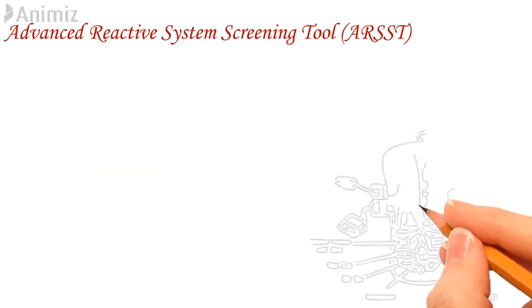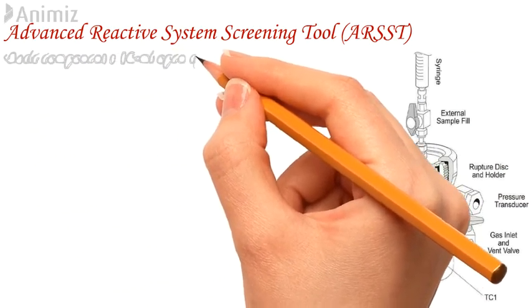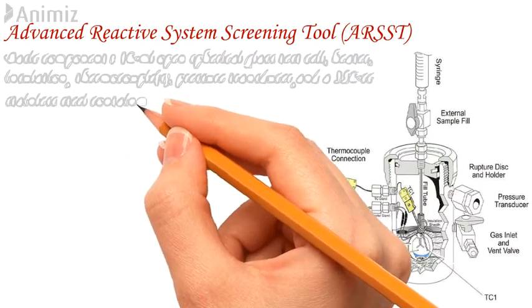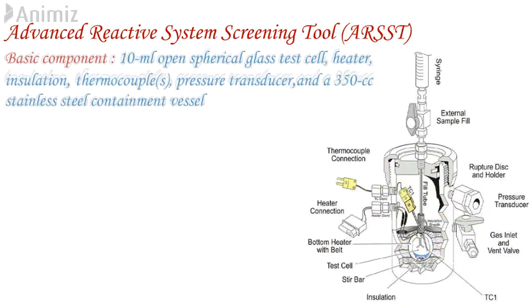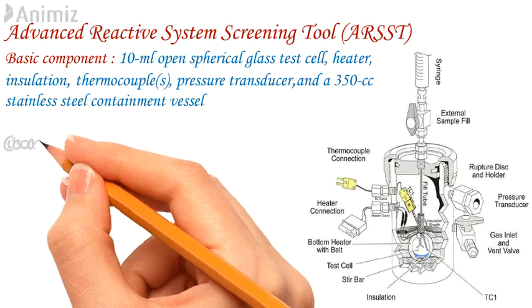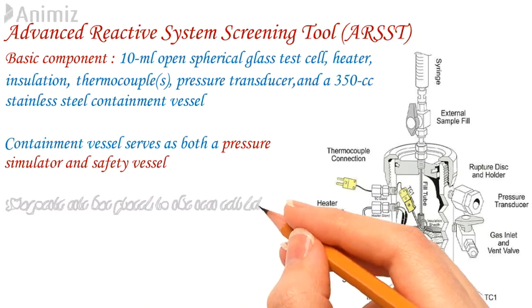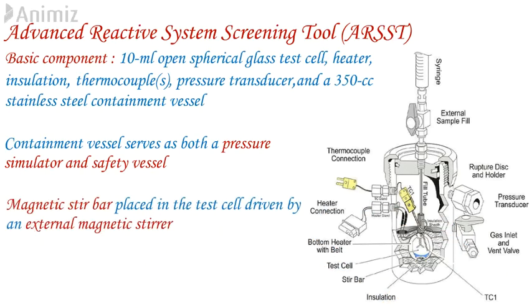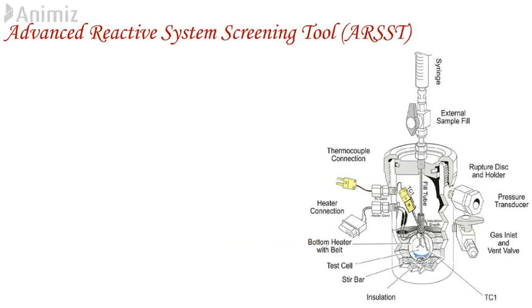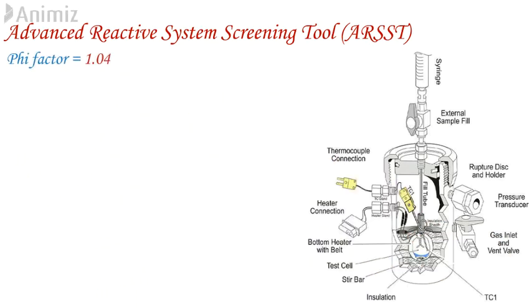The basic components of ARSST include a 10 ml open spherical glass test cell, heater, insulator, thermocouple, pressure transducer, and a 350 cc stainless steel containment vessel that serves as both a pressure simulator and safety vessel. A small magnetic stirrer bar is placed in the test cell and driven by an external magnetic stirrer. The external bottom heater is belted directly to the test cell. The apparatus has a low effective heat capacity relative to that of the sample, expressed as a phi factor of about 1.04.